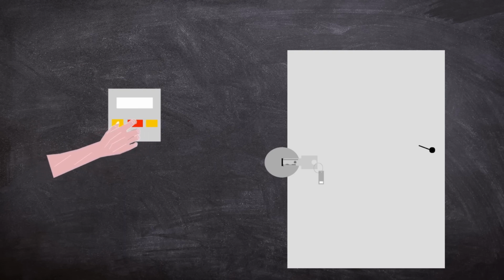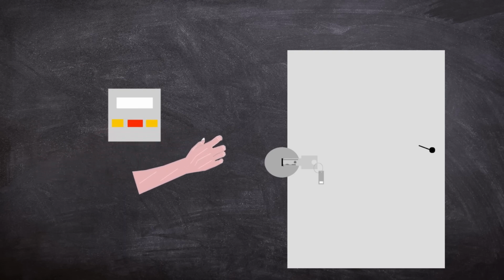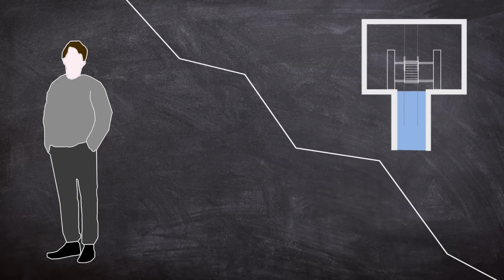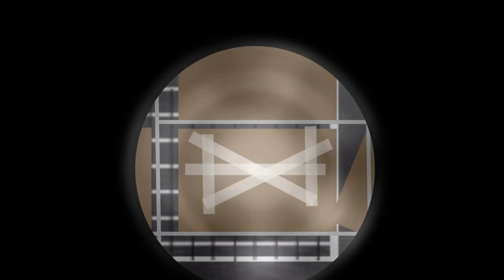This simulated background radiation readings, thus allowing the radiation room to be entered even though the source rack was in the up position. The operator knew the rack was in the up position, but it seems like he was not aware of the dangers this posed, as his next move was to cut power to the radiation machine and enter the room. He did not check the radiation level.